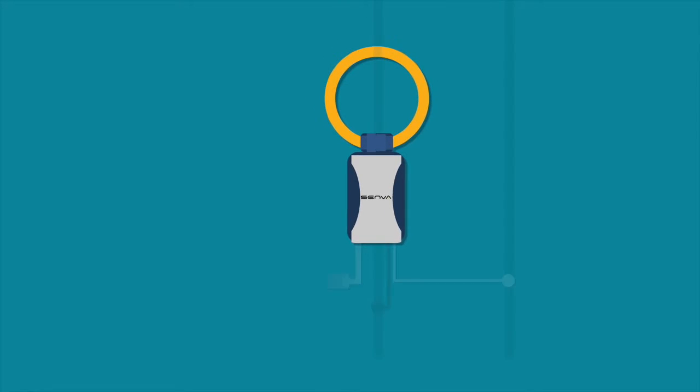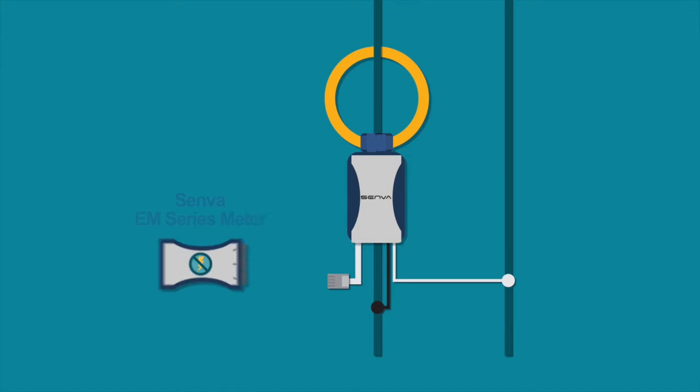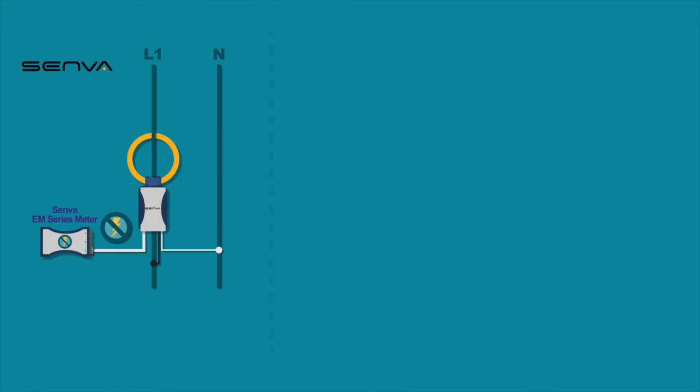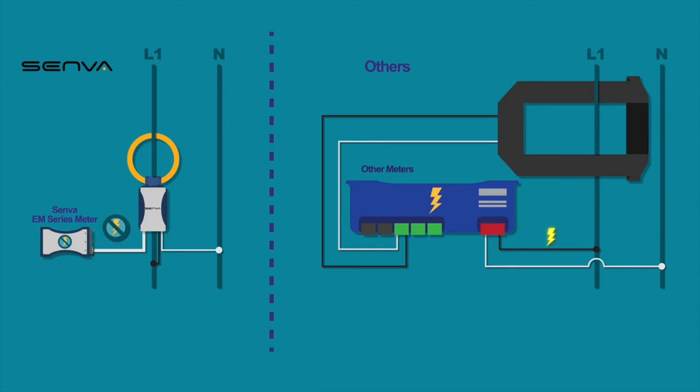The safety feature on the EMRS 45 meter begins with Senva's Current Voltage Transducer, or CVT. CVTs are designed to keep the high voltage connections at the CT level and away from the meter, making the EMRS 45 a low voltage device. This is safer than traditional meters, which require high voltage connections at their meter base.